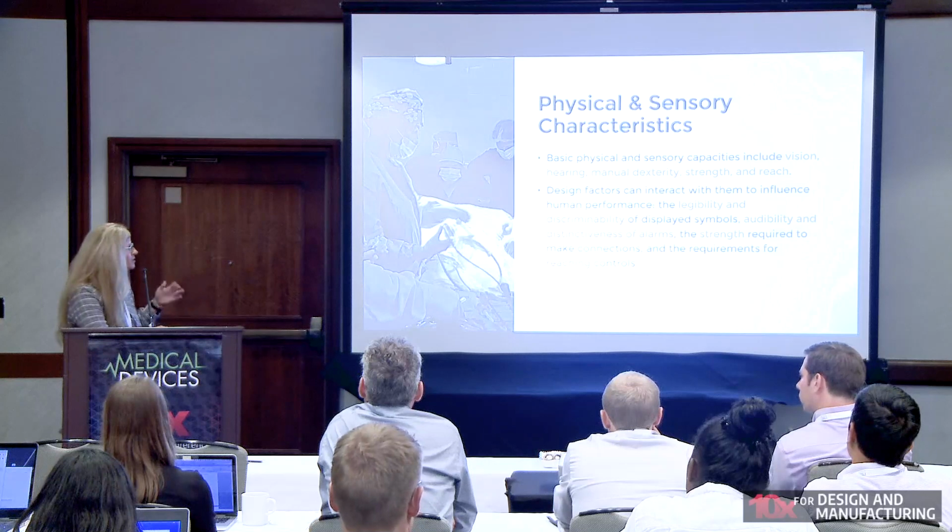Let's just say I'm back at Ethicon and I'm designing a linear stapler. And in order to get the linear stapler to fire two lines of staples and cut in the middle, I need to produce 75 pounds of force on this lever, so all the engineers in the room can think about the math, right? It's inputs to outputs when I think about it from an engineering perspective. Well, I'm not physically able to do that if I'm a 50th percentile female. And the reality is that most people going to medical school are increasingly women. So it was designed for men, but now it's for women. So that's when gender, size, all of the biomechanics come into play to impact the overall usability of a design. So it's important to pay attention to that.